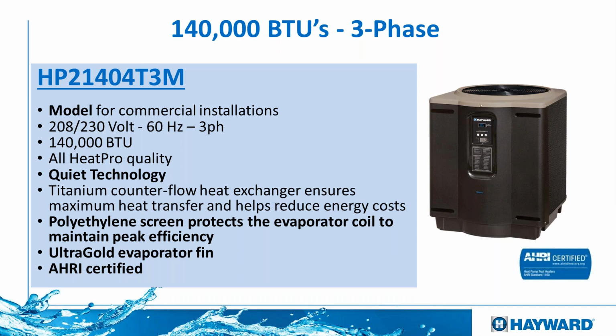This three-phase unit is great for commercial installations where we have three-phase power available. Remember that every time we are doing an installation with three-phase, the power is actually more stable. We don't get the wide variations that we can get on single phase. So I recommend that every time you're doing a commercial project with three-phase, you use a three-phase unit, and that is going to give us fewer headaches, especially with power spikes and power drops and so on. And remember, we're going to see a little bit later when it comes to installation, that if we have a commercial project with a very large pool, we can actually install multiple heat pumps in order to keep those pools warm.